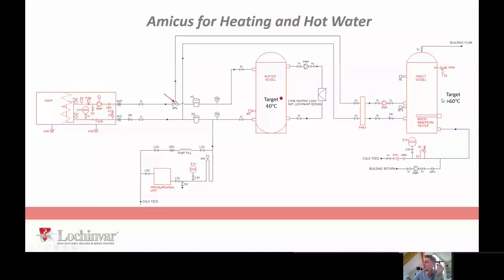So that's an example of how a heating and hot water application would work from a single air source heat pump. Now, that could, of course, be 4 air source heat pumps just in a reverse return format. You know, it depends on your load-ins, how many points of failure you want, how much resilience you want to build into the system. But yeah, these options are all there.